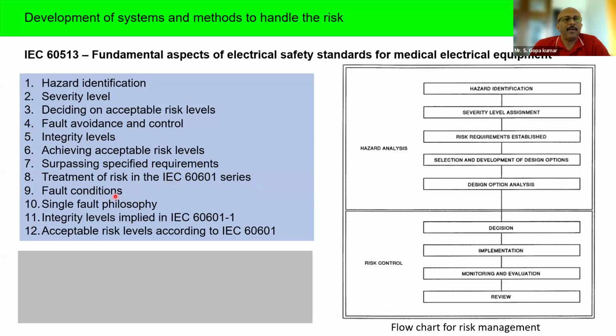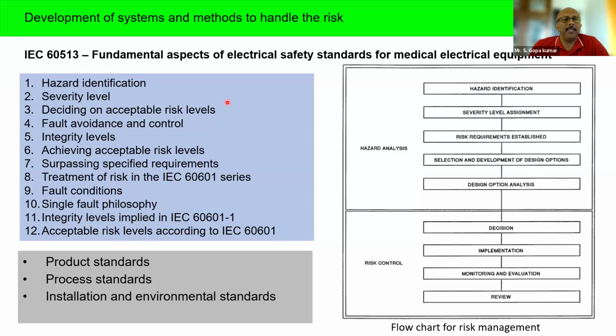Fault conditions are defined in the standard: single fault philosophy, very important. Single fault philosophy. I will show you the definition of single fault later. So basically, based on this risk assessment, product standards are developed, for example IEC 60601. Process standards are developed. Installation and environmental standards are made, and application standards are developed.